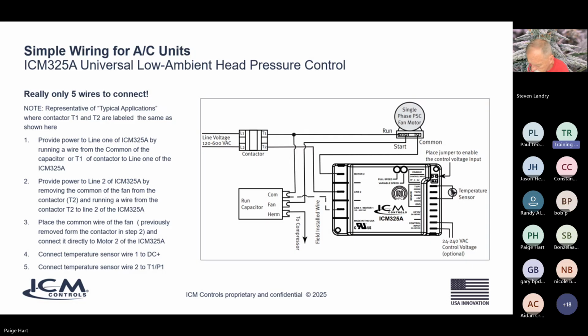So you see line 1 simply connects to the common of the capacitor. Not all of these are going to have a single permanent split capacitor fan motor, so you're going to have this capacitor. It'll either be a dual run capacitor like you see here, or you might see a standard start capacitor, but most of the time you're going to see a dual run capacitor like you see here. So the HERM is just going out to the compressor. All we're really concerned about is the 2 terminals for the common of the fan.